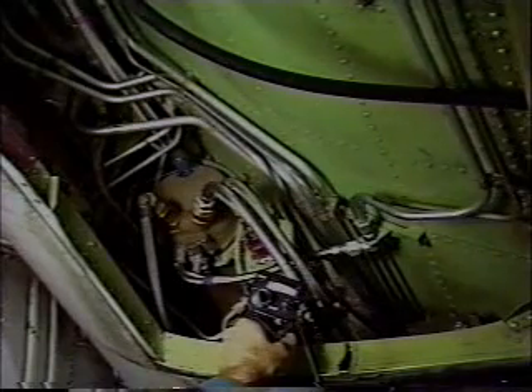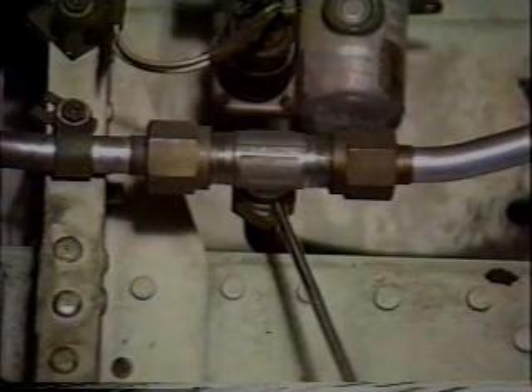Ultrasonic warning signals can also be effective in checking hydraulic and mechanical systems. They can indicate a potential problem before it could be detected by heat sensing or by vibration instruments. For this type of testing and troubleshooting, the ultraprobe is used with the contact probe. The contact probe is used to check pumps for cavitation, to check the direction of blow-by in a two-way valve, to detect and pinpoint bypassing check valves in hydraulic systems, and to internally check anything mechanical such as gears, motors, pumps, and bearings.